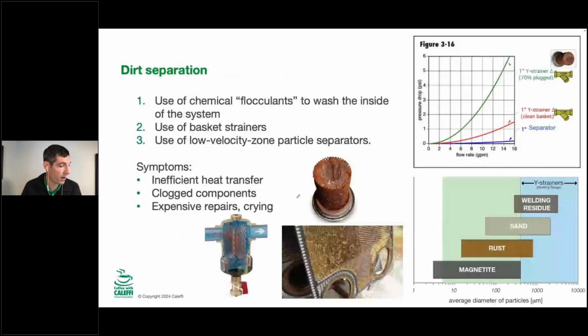Okay, we are at the end of the presentation here, so I'll go through these a little bit quicker. Dirt separation, same concept. We've got a big open vessel here that slows down the fluid coming in, so we're able to separate the dirt better, and they don't plug. So as the dirt separates, it's going to come out of the flow path here, where in a Y strainer, it's just always in the way.